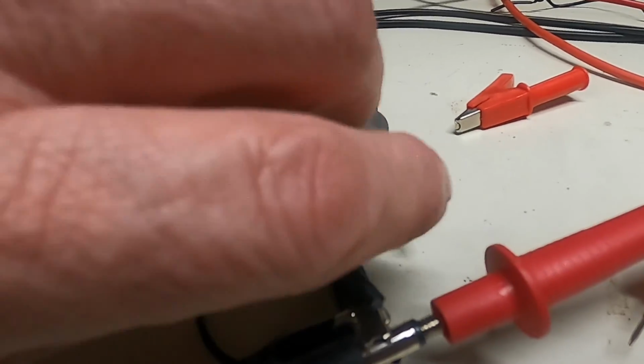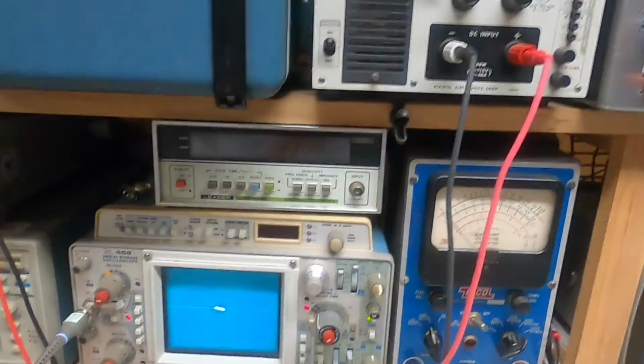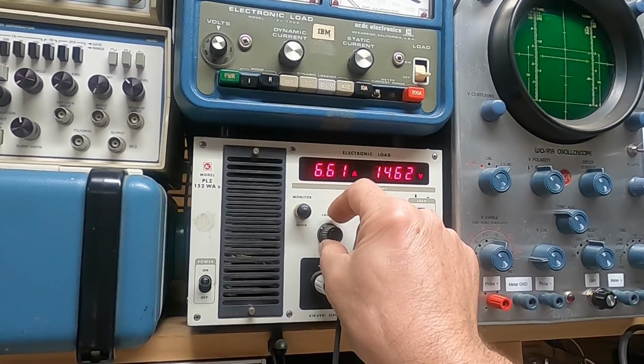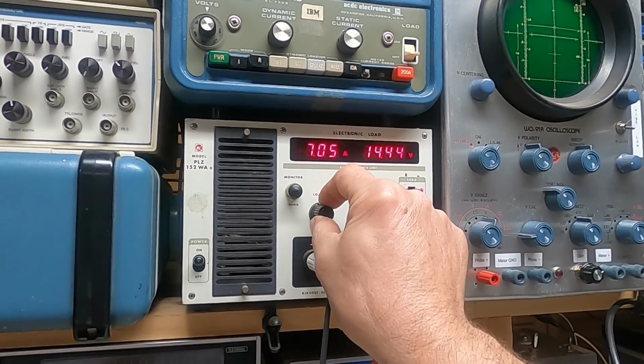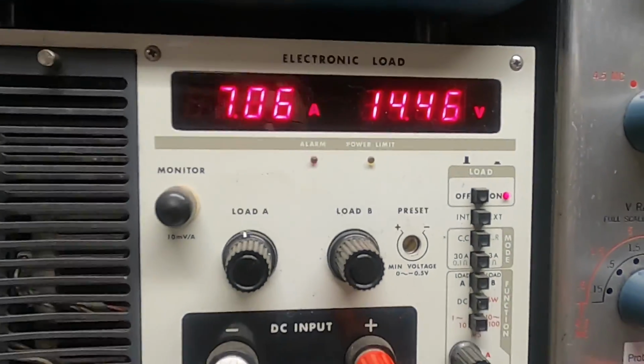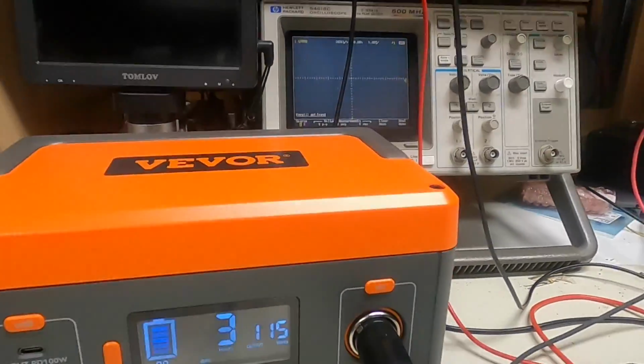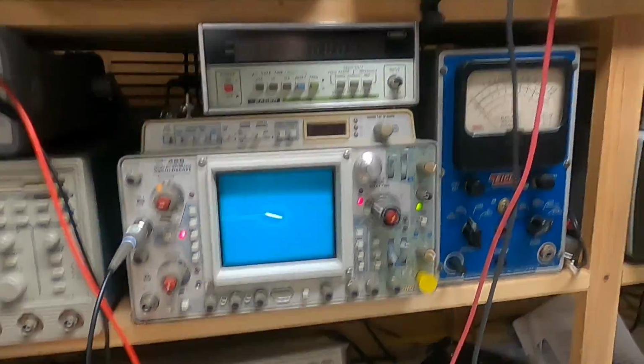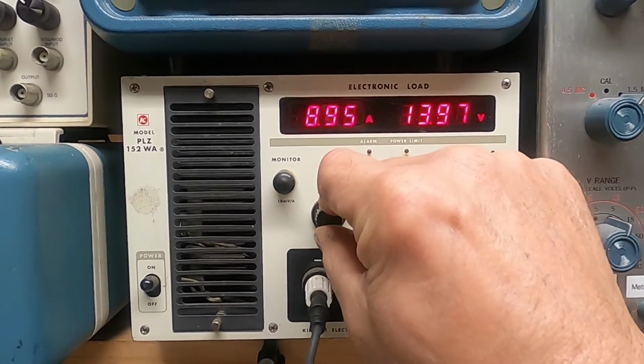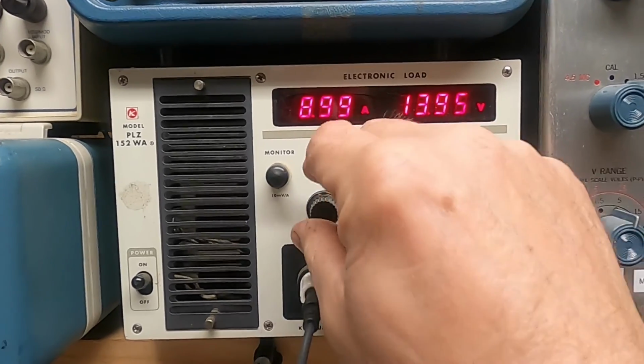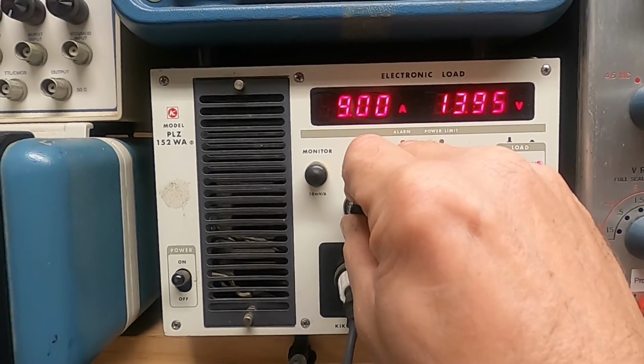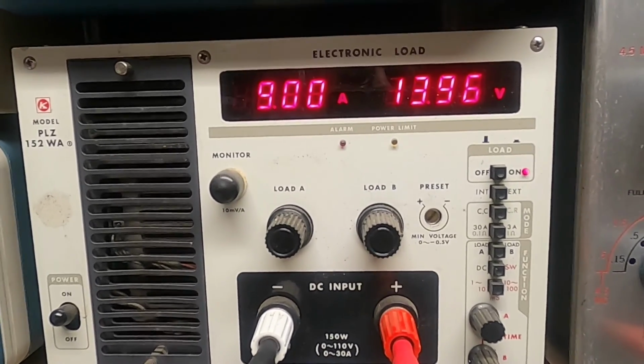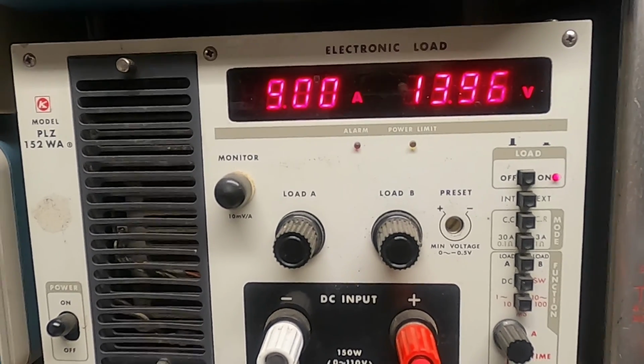And the run hours is now down to 4. Checking, making sure nothing is getting warm. Okay, so probably not going to go too much higher amperage. We'll take it to 7 amps. Voltage is holding pretty good. Okay, so we're going to put this at right around 9 amps. 9 amps. So at 9 amps, the voltage has dropped down, which is to be expected.